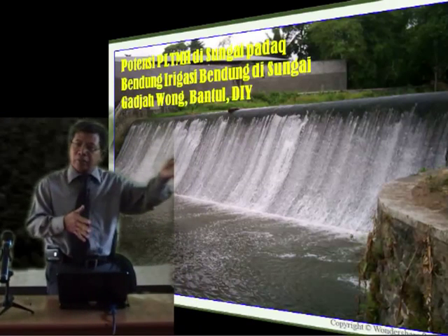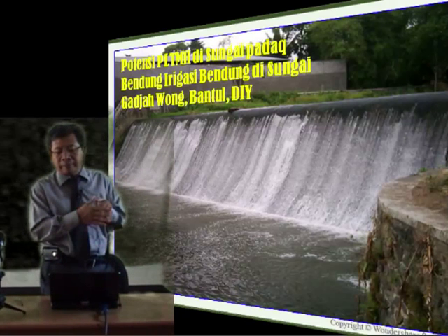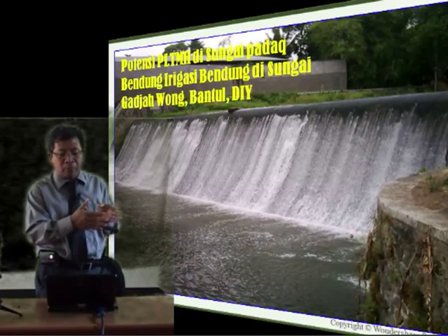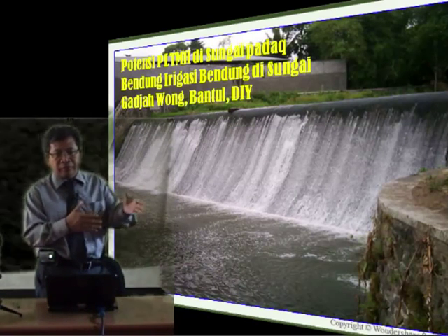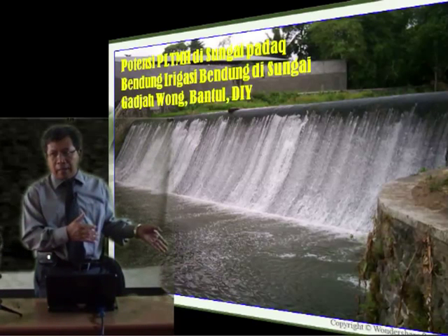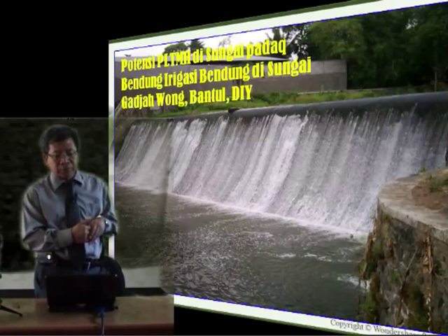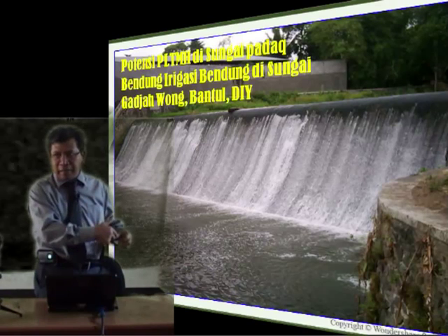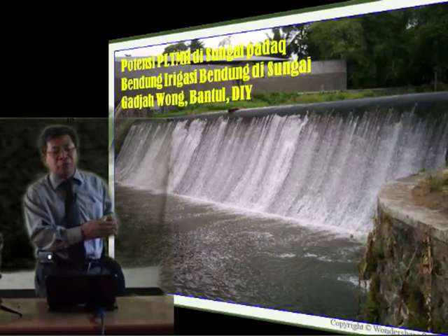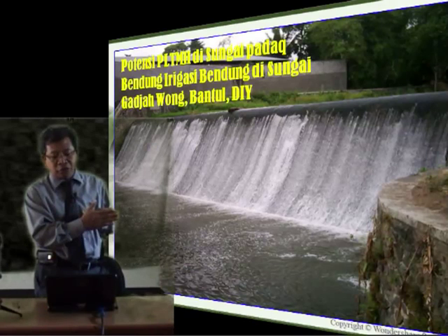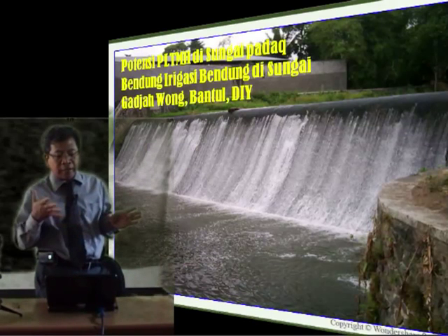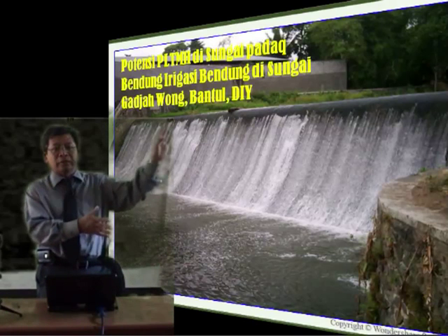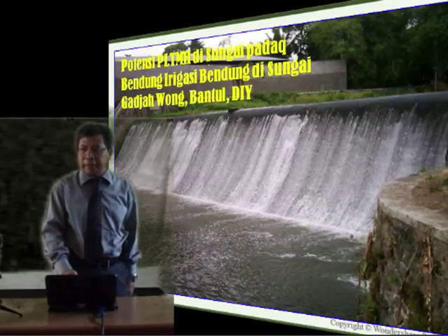The water for irrigation, you let it go, but for example, you develop 50% more from that, so the 50% of water can be used for microhydro. Never take the water that is actually for irrigation for microhydro. No, you have to make the intake channel wider in order to have more water, and then the rest of the water can be used for microhydro. The other water can always be used for the irrigation system.